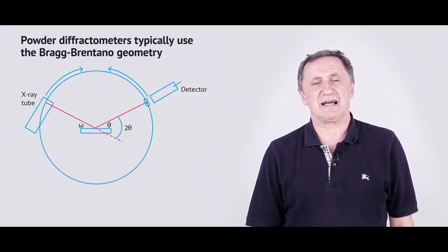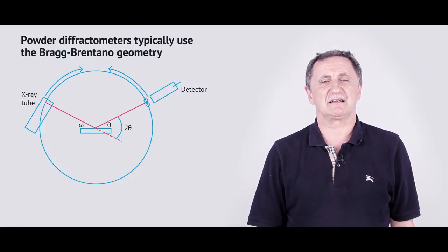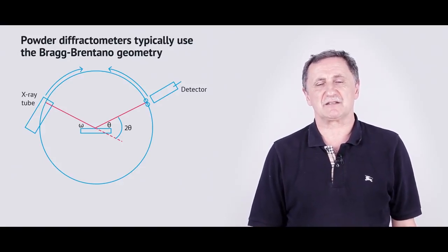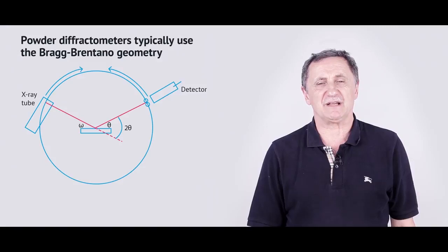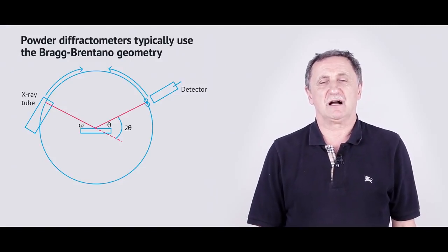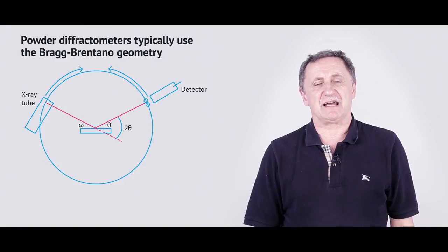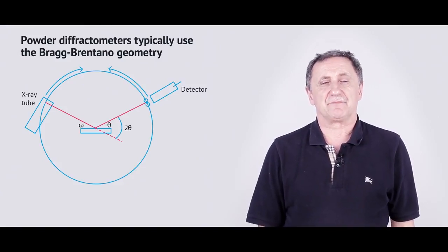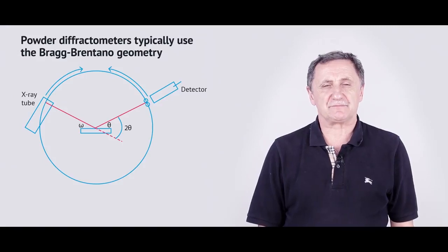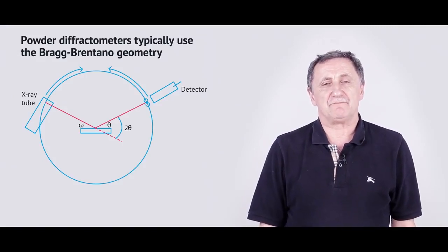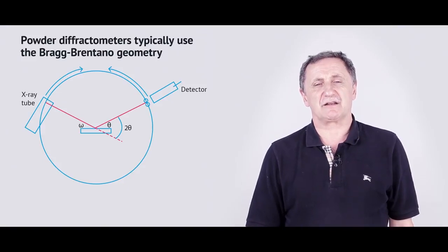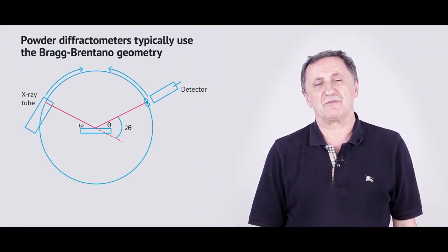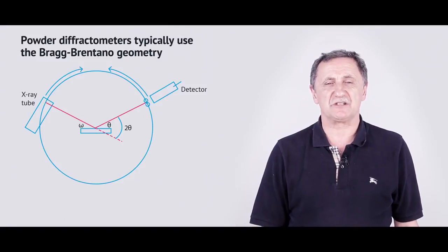We have our sample nicely located inside the XRD machine, and you have a detector which generally moves along our sample and detects the number of photons at a special diffraction angle theta. So actually that's it. The typical time for obtaining the general information, the XRD pattern, from your sample is on the order of 20 to 40 minutes.